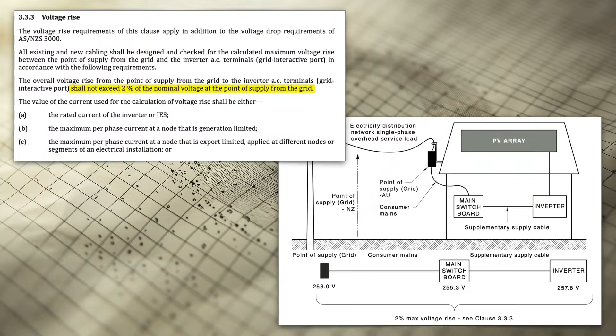And where it can be a problem is where you've got a rural property. You might have the main switchboard at the front gate, 300 metres of underground going to the house, and that's where the inverter is. Trying to keep the voltage rise down in that circumstance can be very difficult. Sometimes it's better just to end up putting the inverter and the whole PV system out near the front gate. Yeah. Okay.